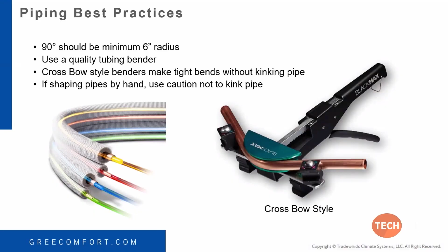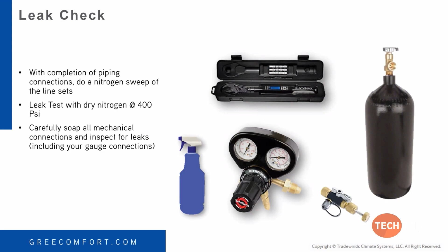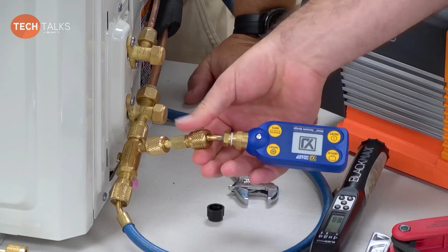All right, we talked about the bender. So now we're at the leak check stage. I know we've already got the vacuum gauge on here just for example. We don't want this on here when we're in the leak test stage, okay? We don't want to damage our vacuum gauge. Now, this particular one I have is rated so that it won't damage it, but I would not have this on there to do the leak test.